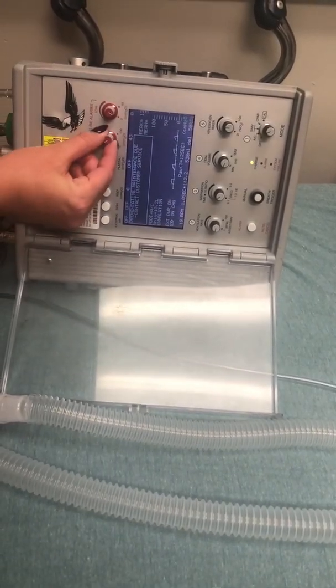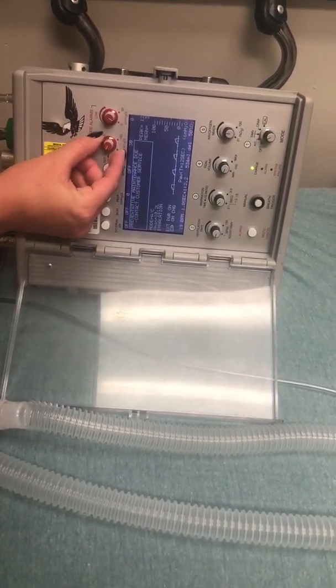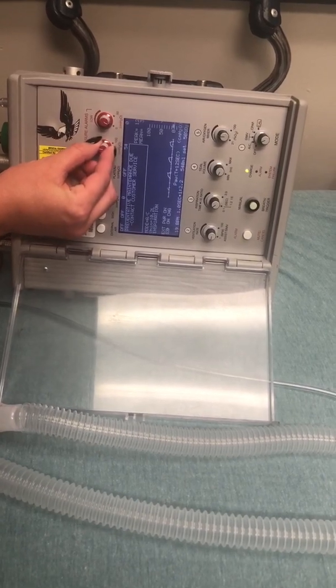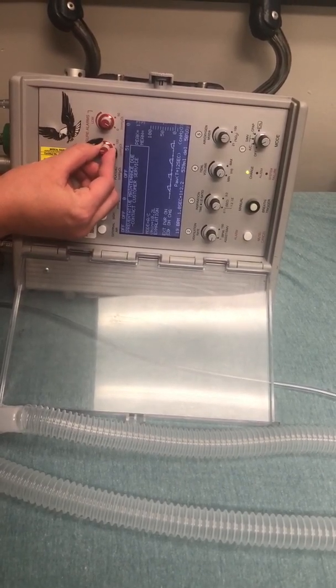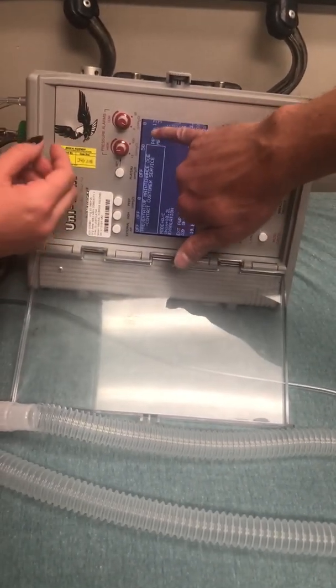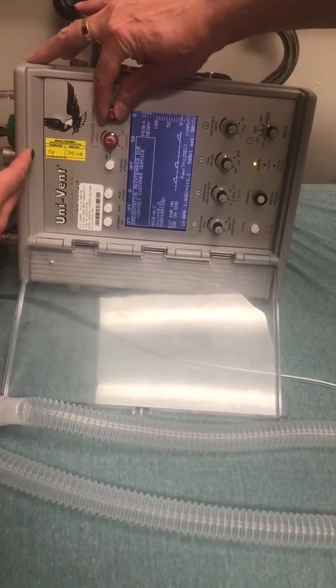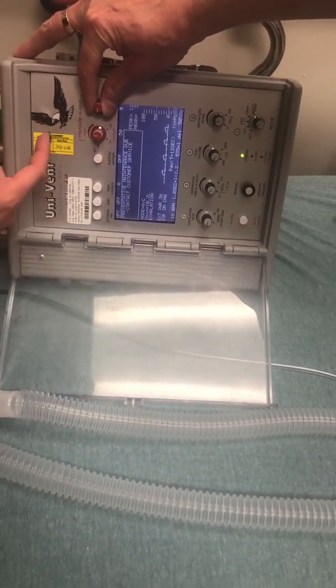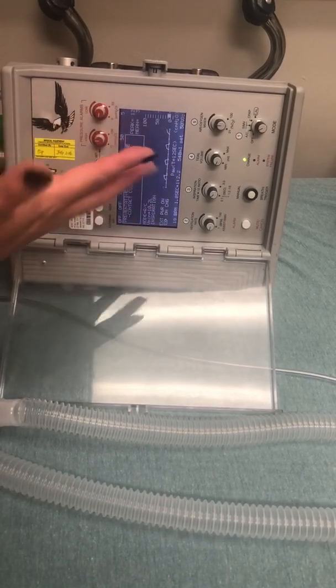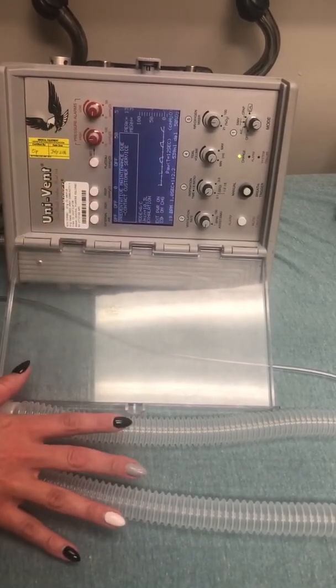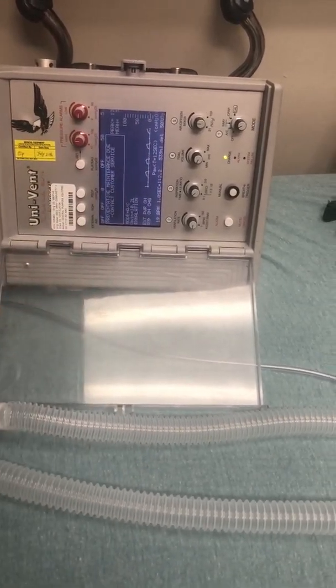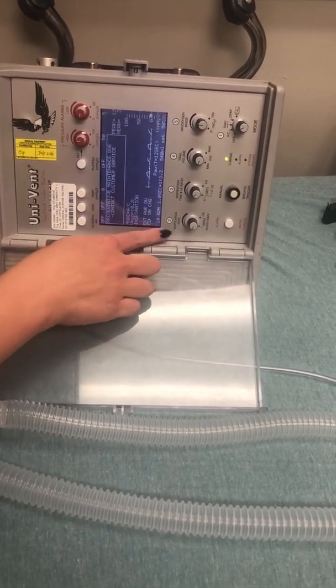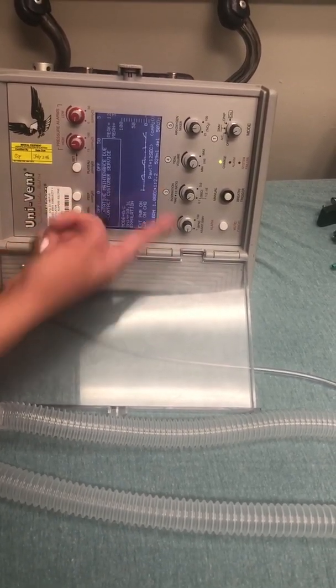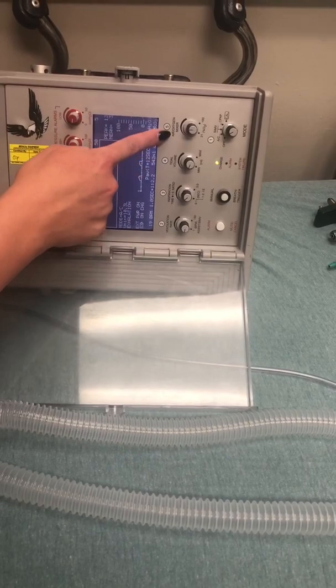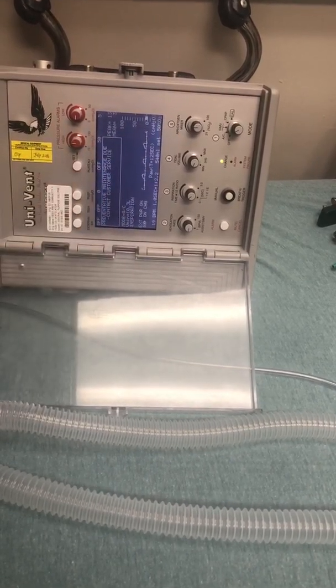Your high pressures, you're going to set, they probably know the stuff to set it at, but we usually do about 45, 50. If the patient's more awake, we can set it lower. It is right there, so you can see the number if you want. And then the low pressure, we would set it like 5 to 10 just to make sure something's not disconnected and we're not noticing it. Then you can change your rate here, your I time, tidal volume, and then you could put how much O2 you want to be feeding in.